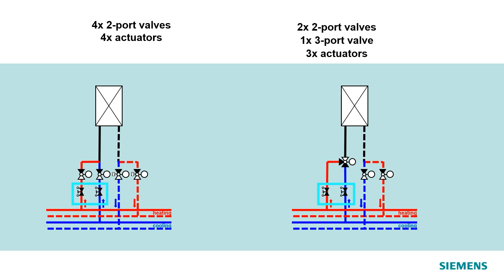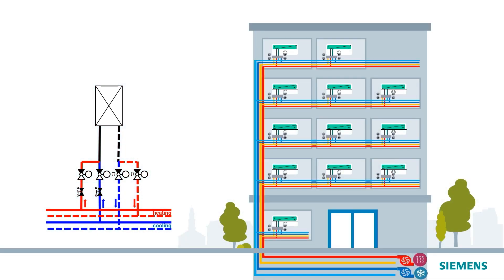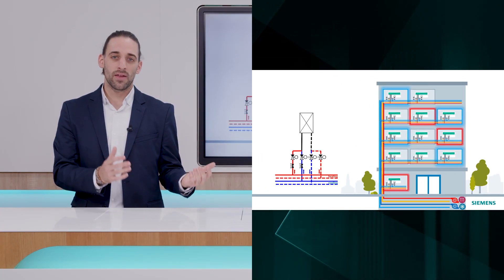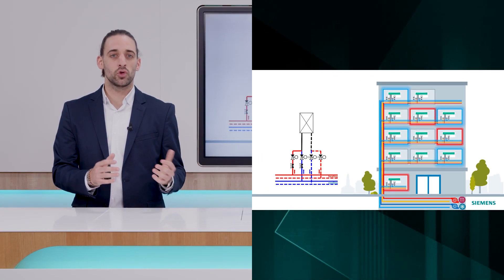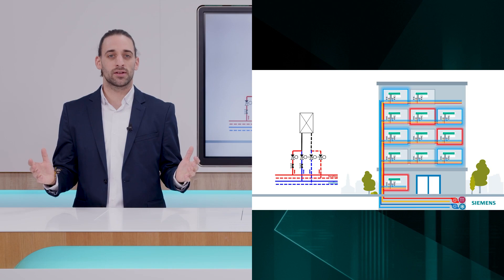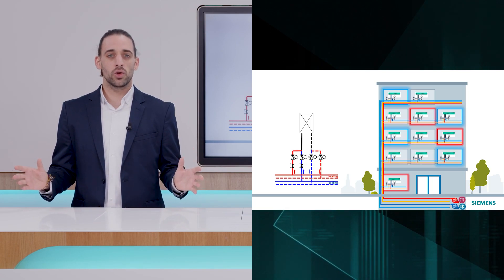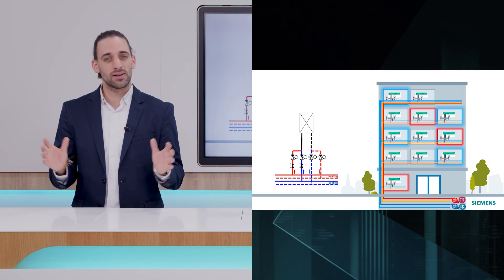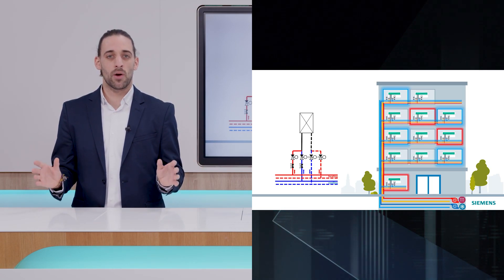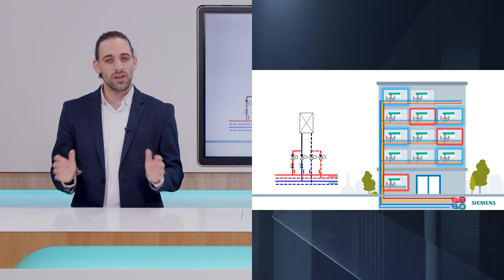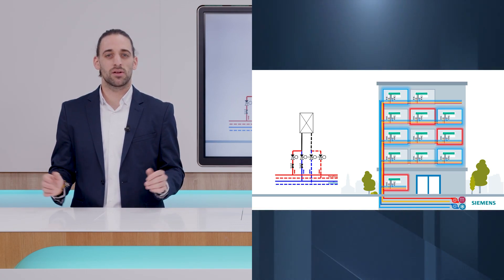Those typically were manual balancing valves that you had to individually commission. Cooling applications typically presented higher flow than heating to meet the comfort demand due to the different delta T. Because of that, you had to separately set the manual balancing valve based on different requirements.